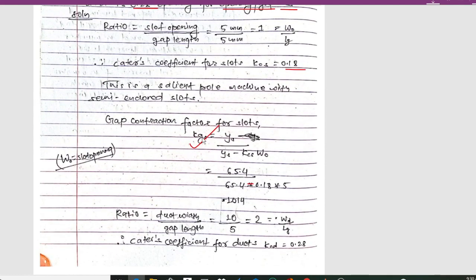Now the gap contraction factor for the slot, Kgs = ys / (ys − Kcs × w0), where ys is the slot pitch = 65.4 mm, Kcs = 0.18, and w0 is the slot opening = 5 mm. This gives a gap contraction factor for slot of 1.014.